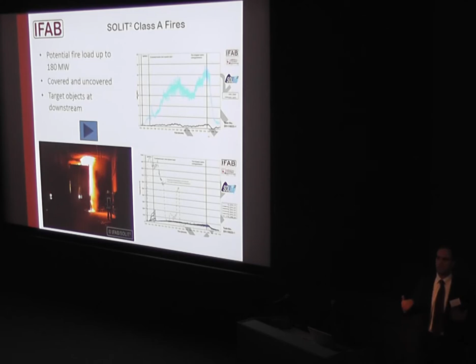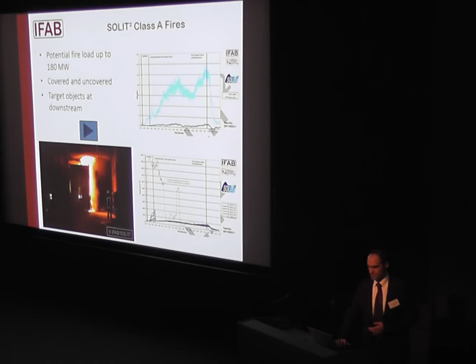But what happens? The fire is detected by a detection system, the system is activated, and then you see the heat release rate. Forget about this first peak, it's again because of the mixture of everything, the fire is still growing. And that's also what you see inside the tunnel. When you stand there, you can see the fire is still growing, but you can walk around this fire. You can really walk around a 20, 40, 50 megawatt load without, I would not say any problem, but if you wear firefighting clothes and a breathing apparatus, you can walk around. And if you can walk around, then any firefighter, even after 20 or 30 minutes, can come there and extinguish the fire. Temperatures, different picture. Immediate cooling, immediate blocking of the radiant heat.